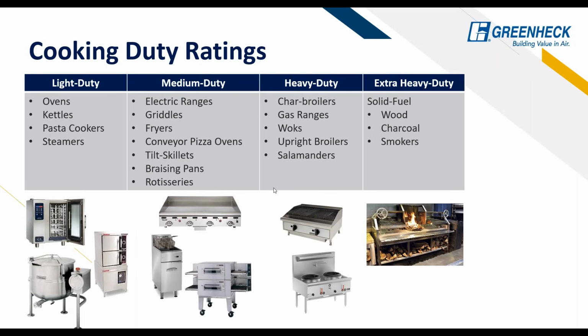Okay, so cooking duty ratings. So we go from light duty to extra heavy duty, and these just depend on which appliances you're looking at. So the electric range will be in the medium duties, ovens in light duties, anywhere from the solid fuels up to the extra heavy duties. Solid fuel is a whole other ball game. You really have to be careful with solid fuels. It's a very, very high fire risk. They require their own dedicated hood, and you don't want to put them next to fryers or anything, because there are chances of these little embers floating around. So they require their own hood.